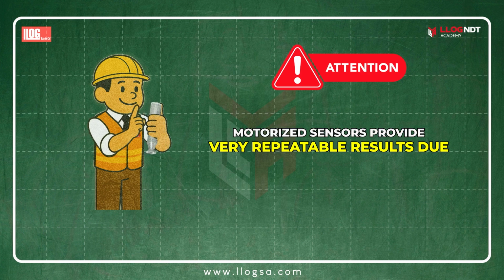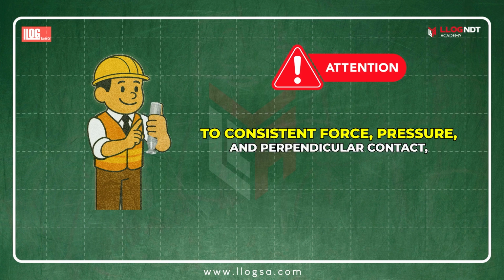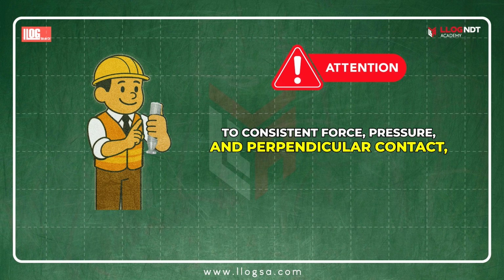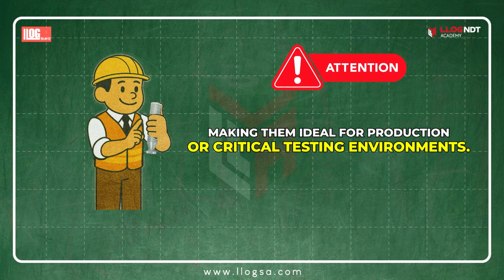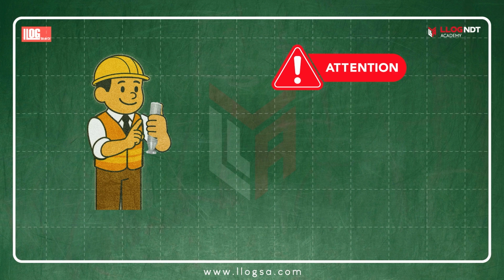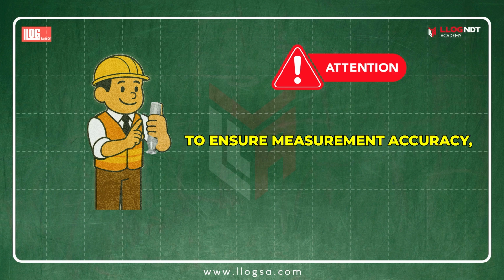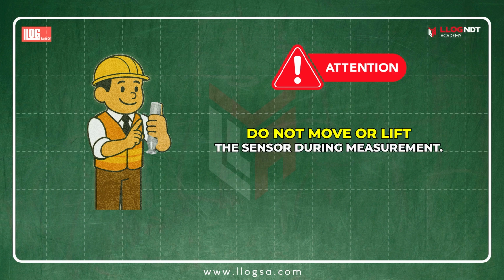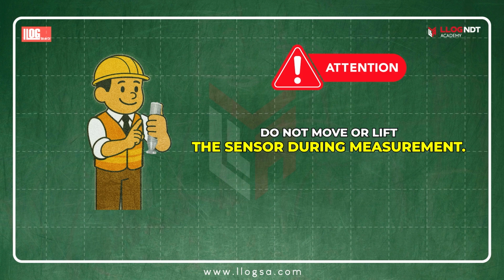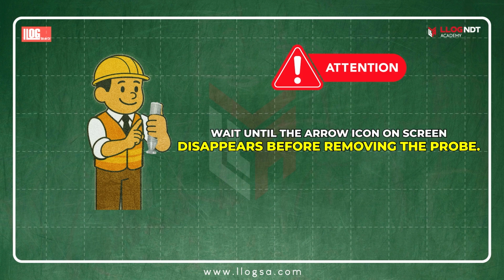Motorized sensors provide very repeatable results due to consistent force, pressure, and perpendicular contact, making them ideal for production or critical testing environments. To ensure measurement accuracy, do not move or lift the sensor during measurement. Wait until the arrow icon on screen disappears before removing the probe.